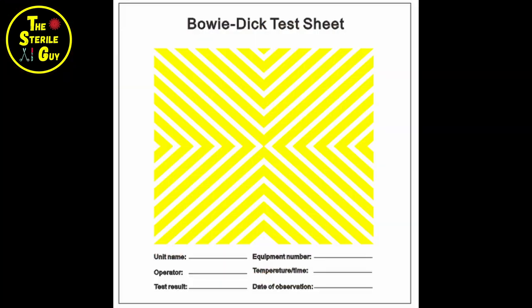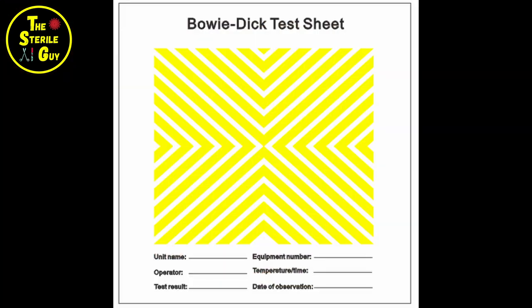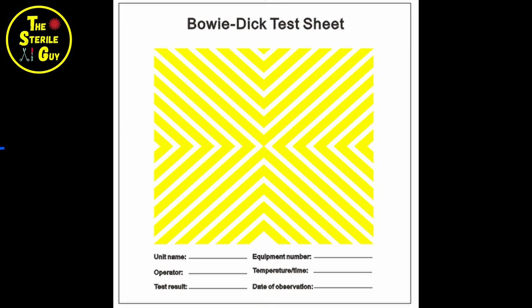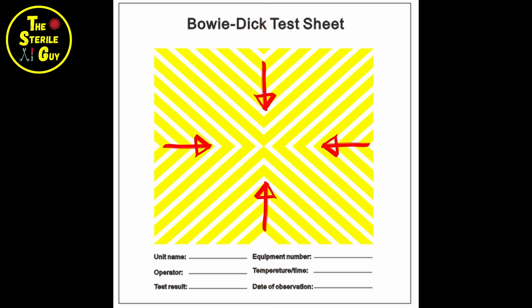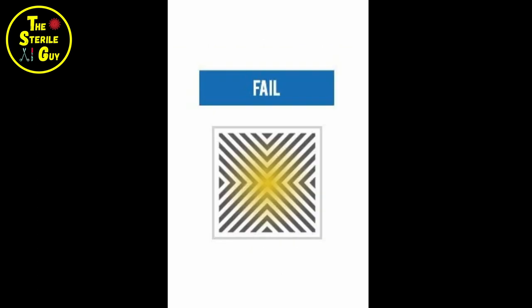The Bowie-Dick works in a similar fashion. The Bowie-Dick is basically a deck of cards with a steam indicator card in the very center. All the cards have some air between them and in the wrap as well. Same process: the vacuum pump pulls all the air out and then steam penetrates deep into the pack. If not all the air is removed before steam, your test will look uneven or incomplete — which is a no-go.